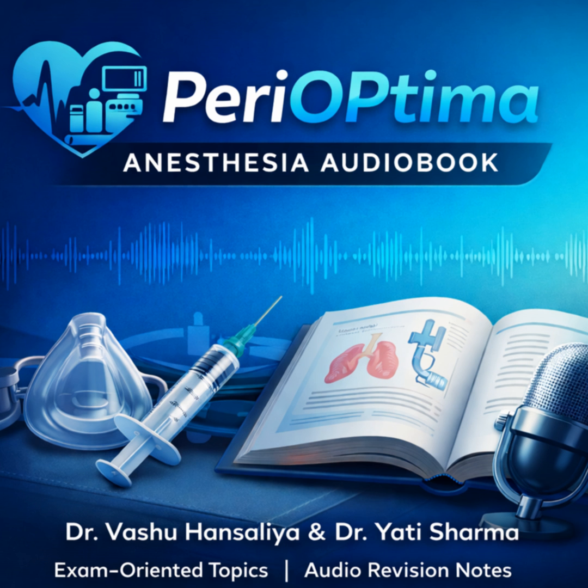Okay, now for the big one. The topic that takes up half the chapter in Miller. Electromagnetic interference, or EMI. Specifically, electrocautery. This is public enemy number one for pacemakers in the operating room. The cautery tip delivers high-frequency radiofrequency energy to cut or coagulate tissue. How does that confuse the pacemaker? It can cause chaos in two main ways.